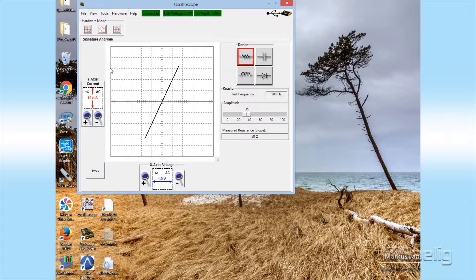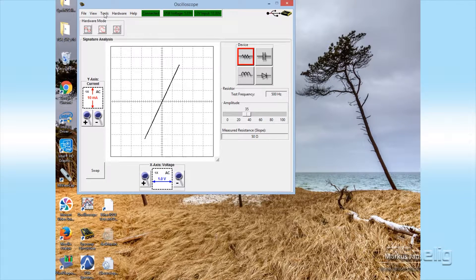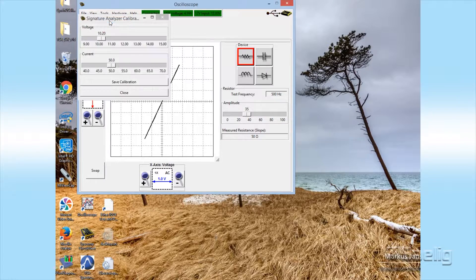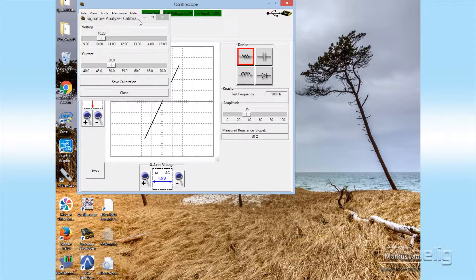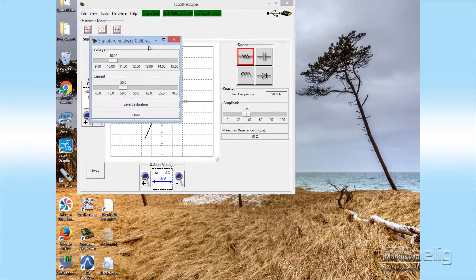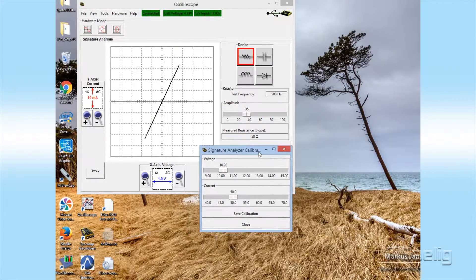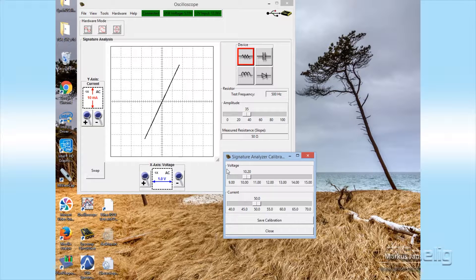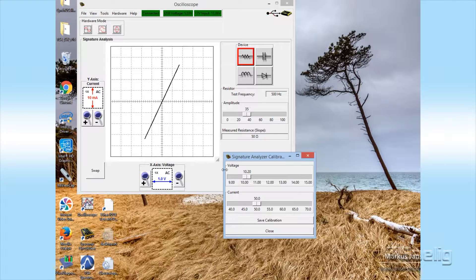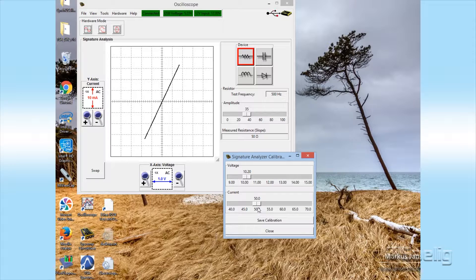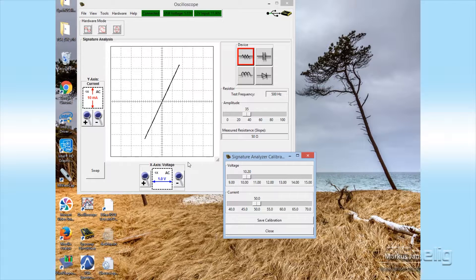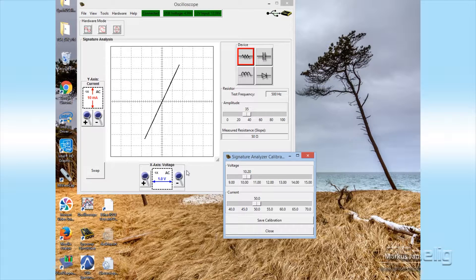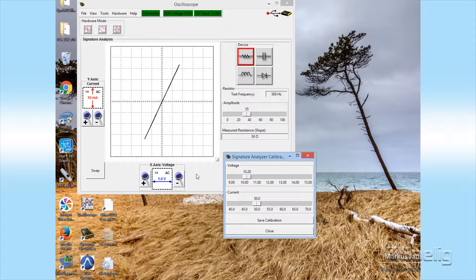As I mentioned earlier, there is a calibration tool for this particular part of the application. You can see it says signature analyzer calibration, and what you can use for this is to set your voltage and your current appropriately using a number of resistors that you have already taken a look at on a good LCR bridge.